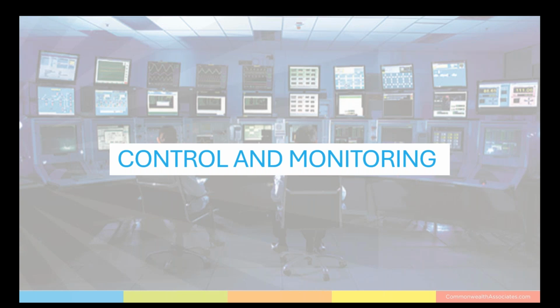To design an efficient and modern control room, there are several considerations that will impact your layout. You must have ancillary equipment, for example, individual UPSs for each critical system, an understanding of where the electrical power is coming from, how the building manages ventilation, and how data cables are routed to and from the room. Other factors to consider that will influence your control room layout are the intangible factors, which are often overlooked initially. These things include aspects such as noise control, lighting in the room, and at the operator level, the grouping of people or workstations, as well as the flow of personnel into and out of the room. And finally, owners and operators often have their own requirements for the control room and admin areas. For example, offices, data closets, and meeting rooms.